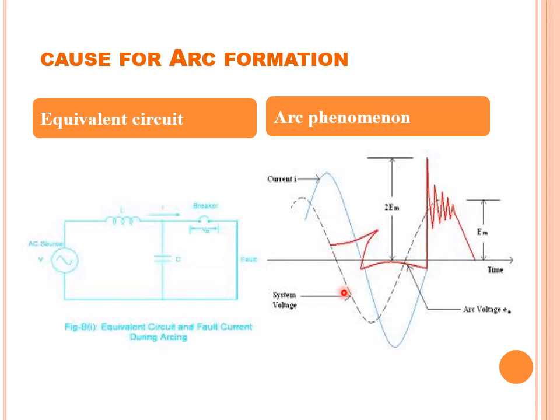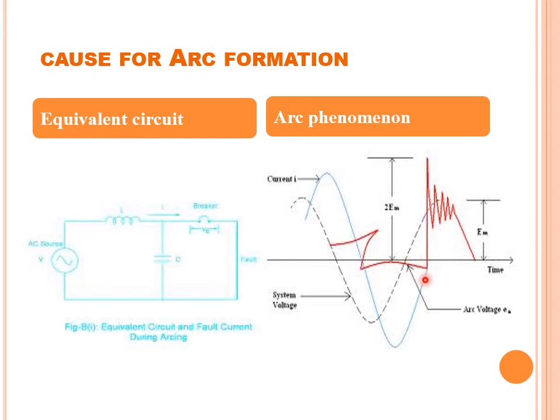Looking at the waveforms: the system voltage and arc voltage with current — the LC circuit forms sinusoidal voltages and sinusoidal current. At the instant current reaches zero, the voltage is fluctuating and there is a doubling effect: a spike rises to twice the peak value Em. This very high voltage must be extinguished, which can be done using methods shown in the next slide.